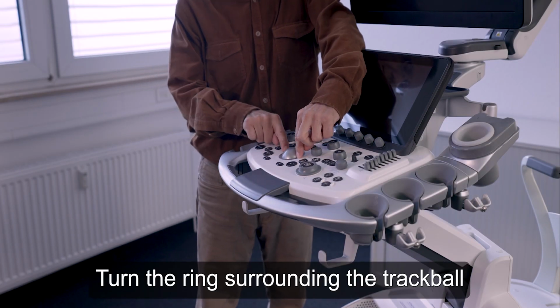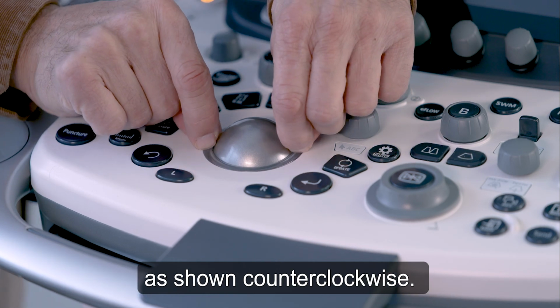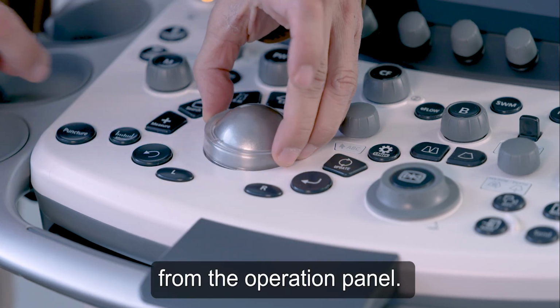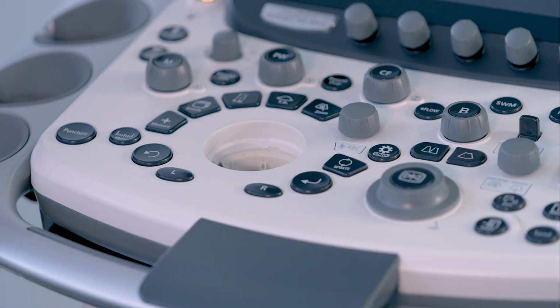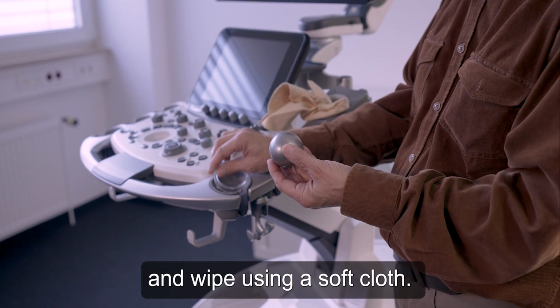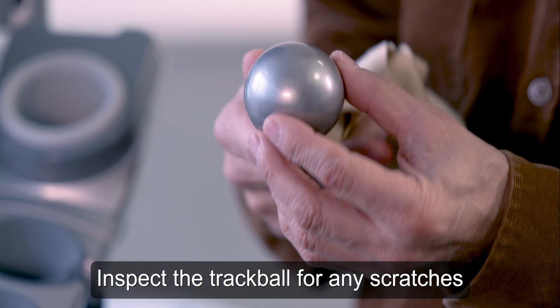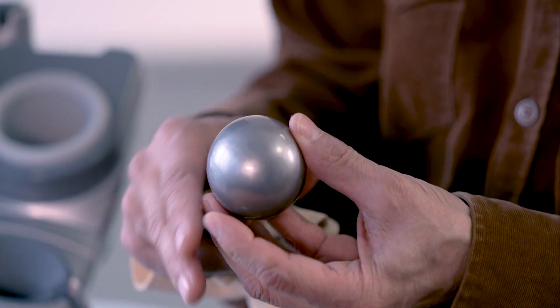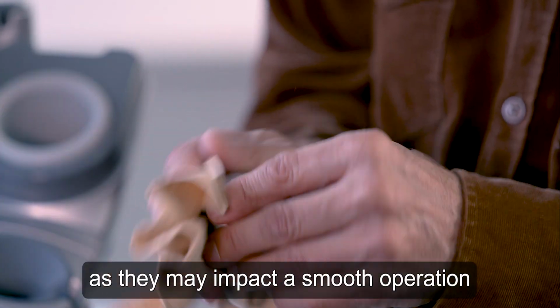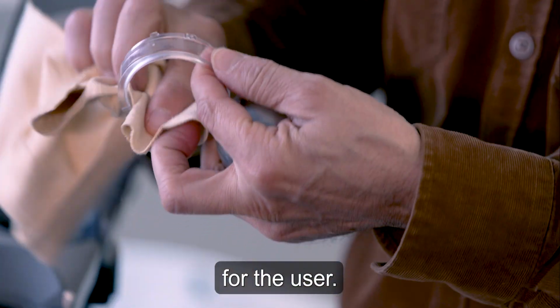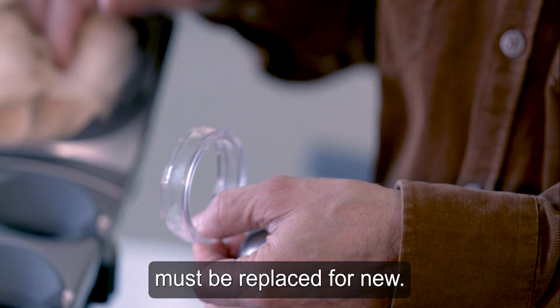Turn the ring surrounding the trackball as shown counterclockwise. Remove the trackball from the operation panel. Remove the trackball from the ring and wipe using a soft cloth. Inspect the trackball for any scratches, as they may impact smooth operation for the user. Damaged trackballs must be replaced with new ones.